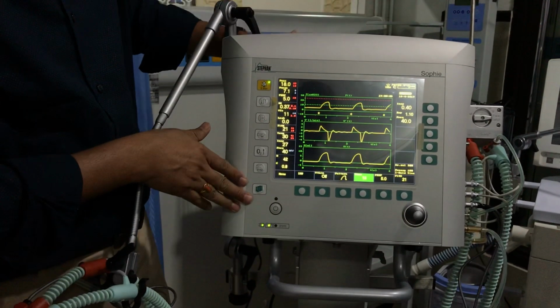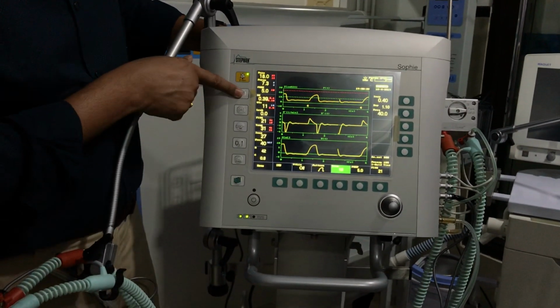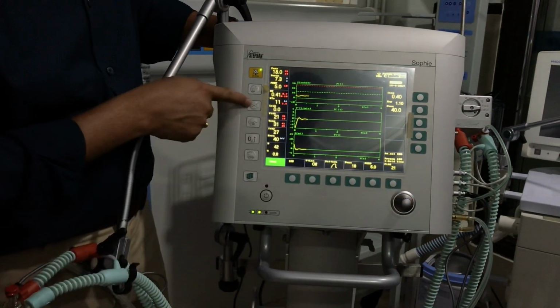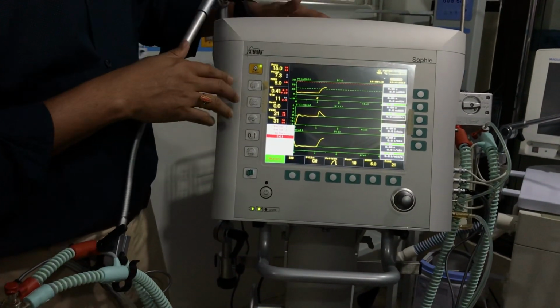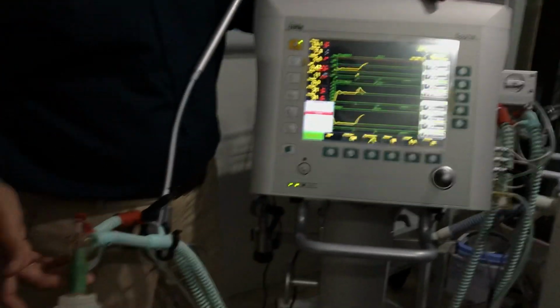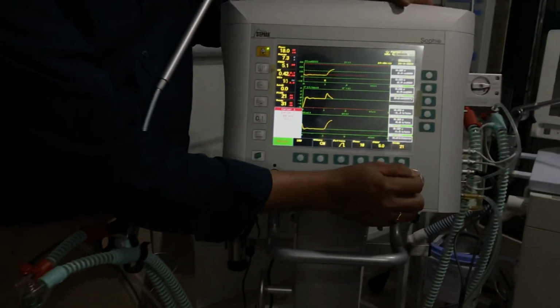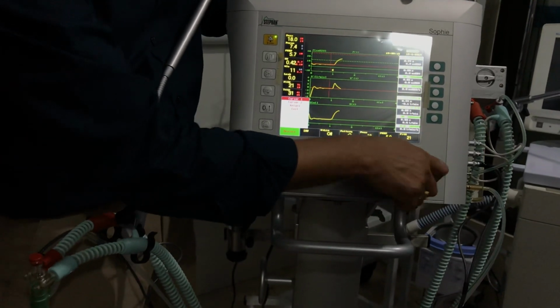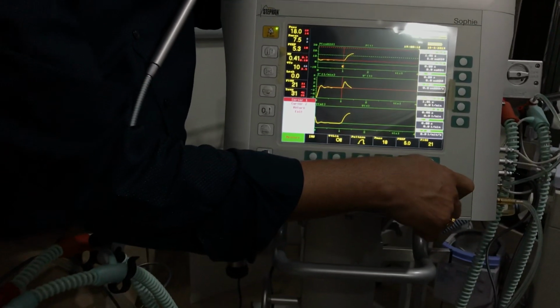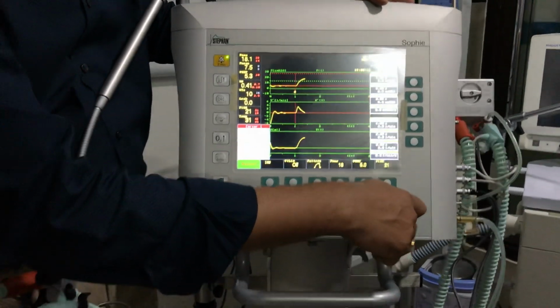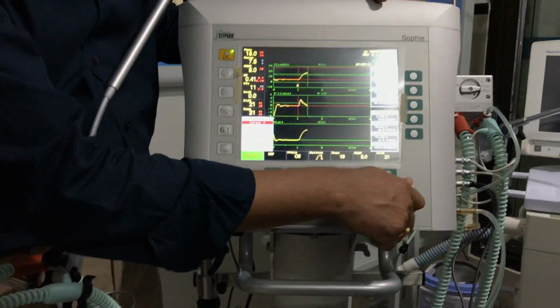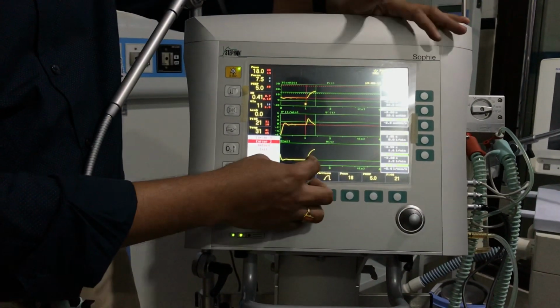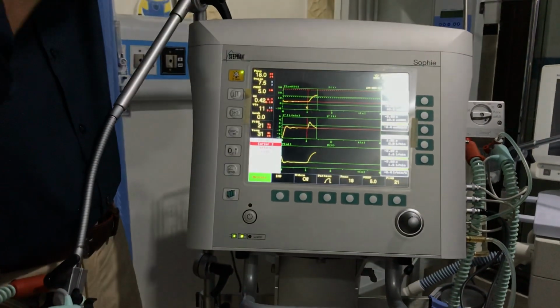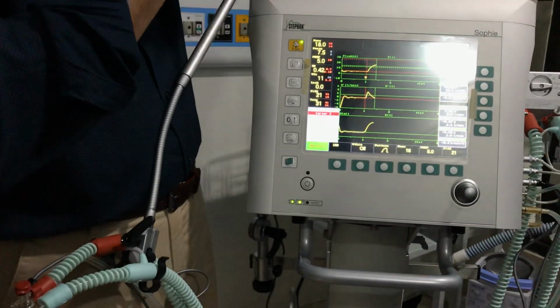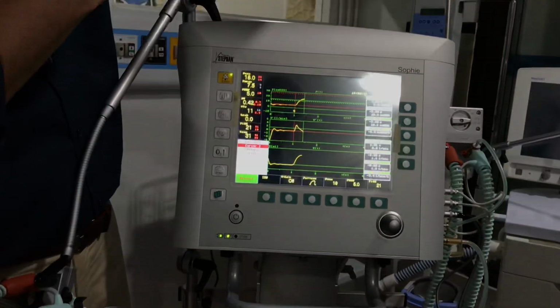Now coming to some basic menu keys here. This is for alarm, automatic alarm setting you can do. Then this is a freeze function. The screen will be frozen, ventilation is continued. Then we have two cursors here. I can take two cursors to any point and measure the values. Just like if I have a loop here, I can freeze this, and I can measure upper and lower inflections. What is optimal PEEP, what is the maximum pressure I can deliver, or where the compliance drop actually started.